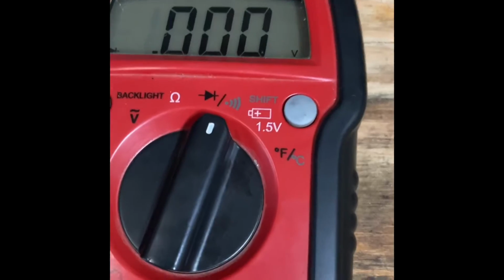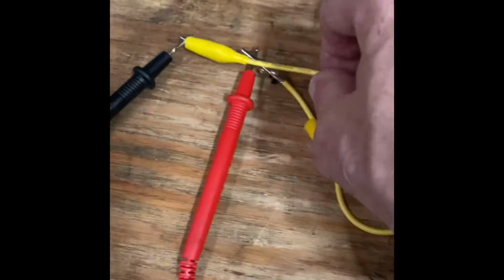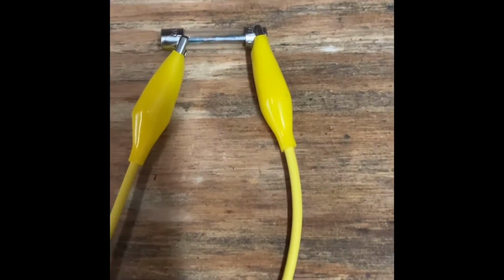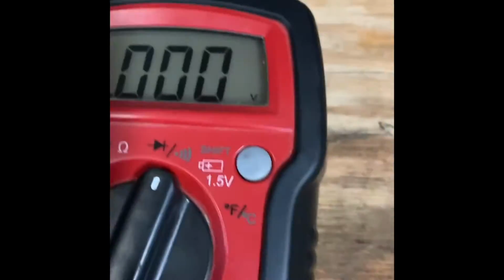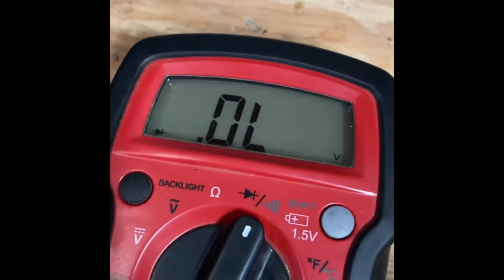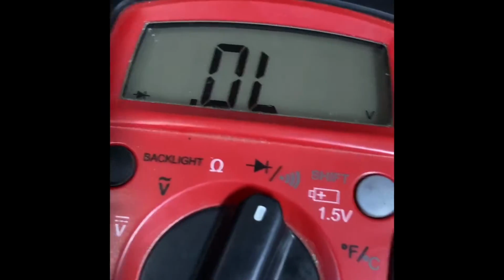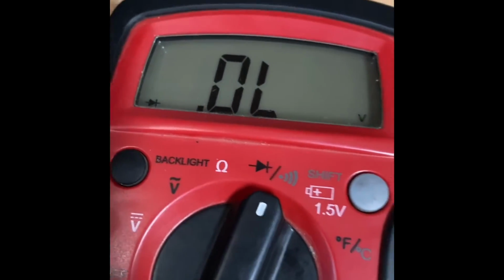I have this on the continuity setting right now. All that's telling me is that I have it hooked up here, doesn't matter red or black, how it goes. With each end hooked up to the fuse, I have 0, 0. If I disconnect one end, or the whole thing, it goes to open line. So if that fuse is blowing, I wouldn't have continuity, I would just stay open. By doing that, I've verified 100% this fuse is good. Now you can look at them and it would probably be cracked in the middle there, but I've had some fuses that looked good but were actually blown. So take the time, double check it, make sure it's good, and you can rule that problem out.